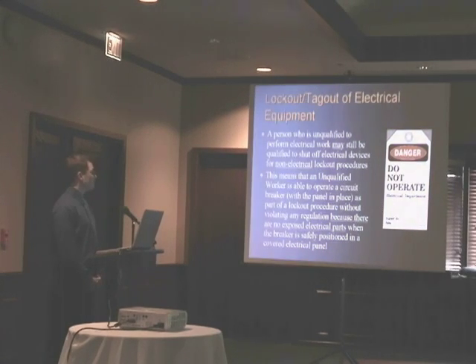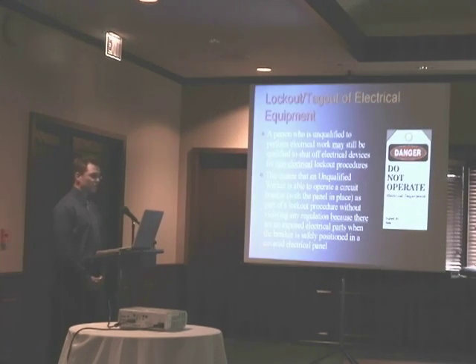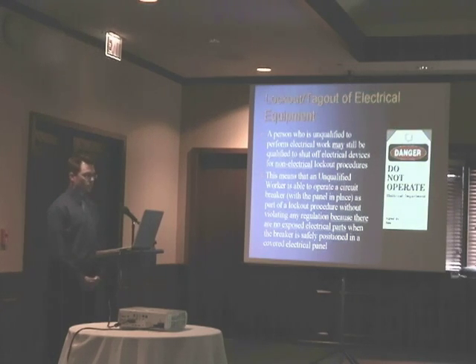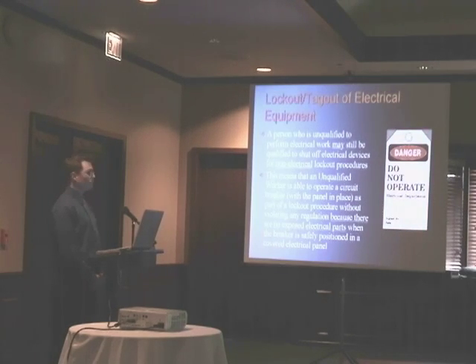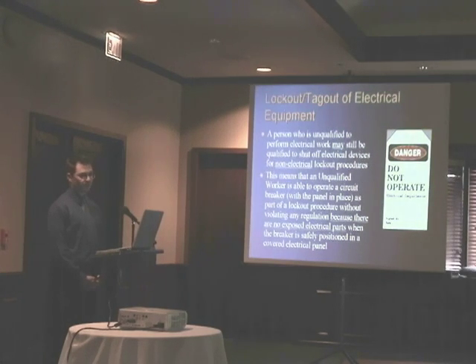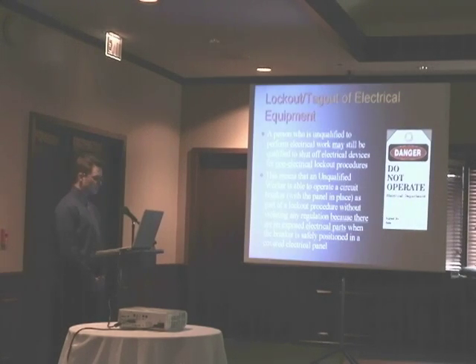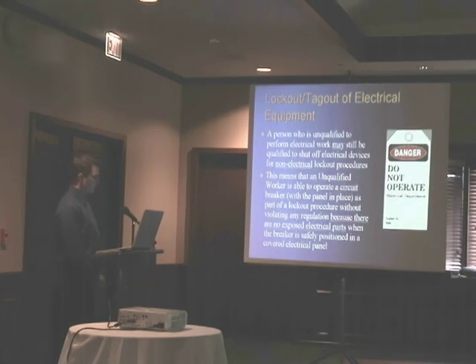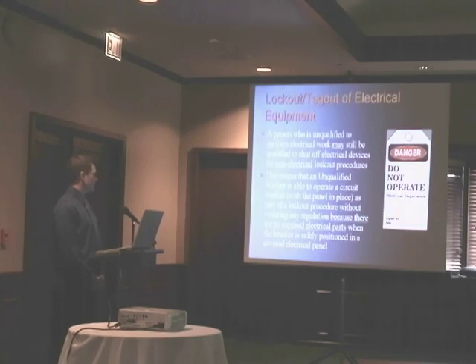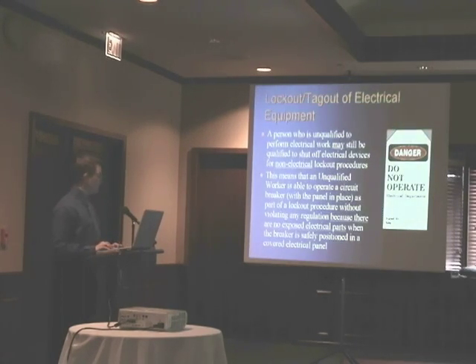A person who is unqualified to perform electrical work may still be qualified to shut off the electrical devices for non-electrical lockout tagout procedures. This is basically stating that an unqualified employee may go to shut off, lock out and tag out a device if he's working on non-electrical lockout procedures. This means that an unqualified worker is able to operate a circuit breaker as part of the lockout procedure without violating any regulation because there are no exposed electrical parts, when the breaker is safely positioned and the electrical panel is covered for him to be able to do this.